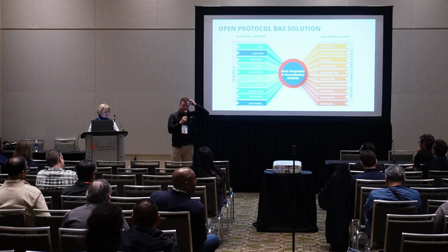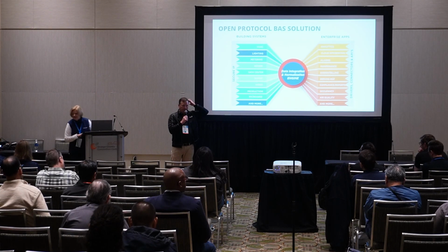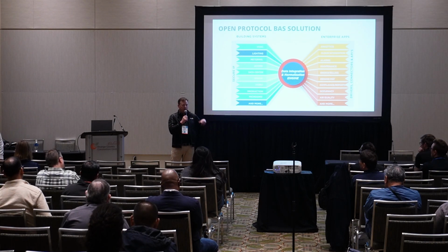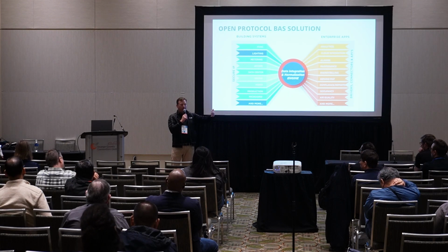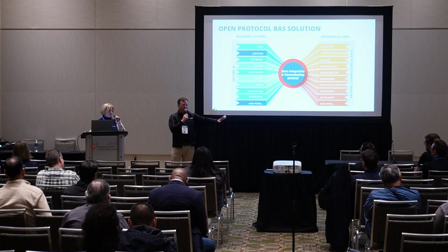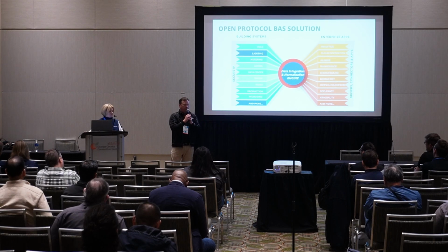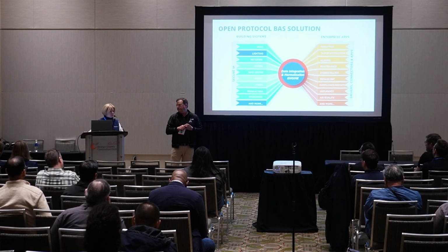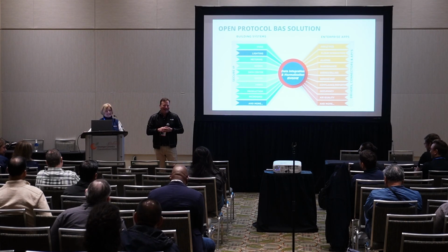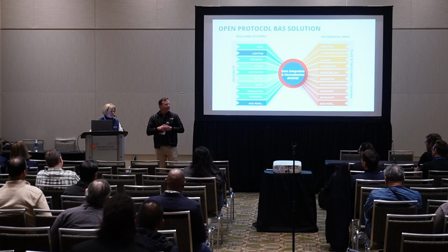The utility integration will not pick up demand; it doesn't pick up real-time demand. So if you're looking to reduce demand charges, or if you're looking more into the real-time granular data of the energy of the building, you have to put your own meter in. If you're looking to do billing type work, or you're looking at the rates and stuff, again, the utility has that info for you. You can also use a pulse output from the meter, which is the technical term. And they communicate too, Modbus. Yes.